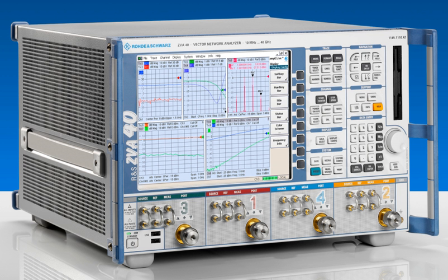http://na.support.keysight.com/pna/caldefs/stddiffs.html. The definitions of the standards for a particular calibration kit will often change depending on the frequency range of the network analyzer. If a calibration kit works to 9 GHz, but a particular network analyzer has a maximum frequency of operation of 3 GHz, then the capacitance of the open standard can approximate it more closely up to 3 GHz, using a different set of coefficients than are necessary to work up to 9 GHz.